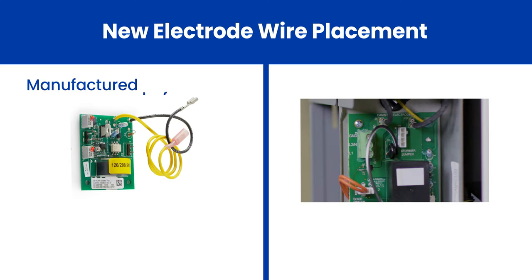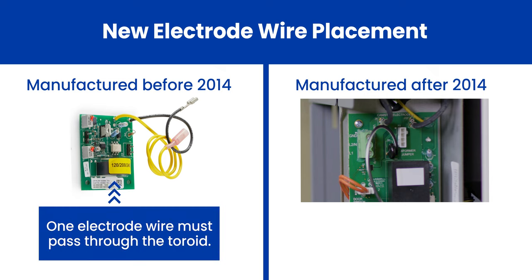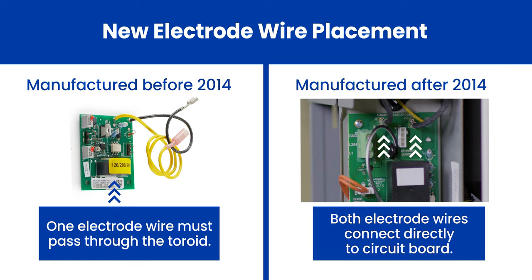For models manufactured prior to November 2014, one of the two new electrode wires will be installed through a large metal ring called the toroid. For models manufactured after November 2014, both wires will plug directly into the printed circuit board.